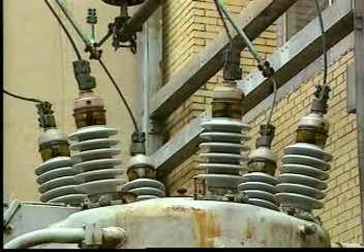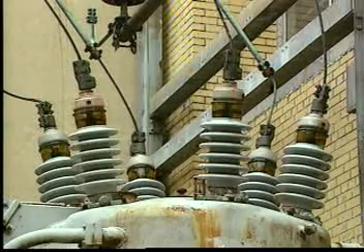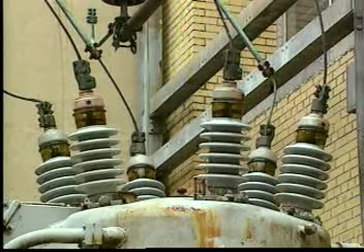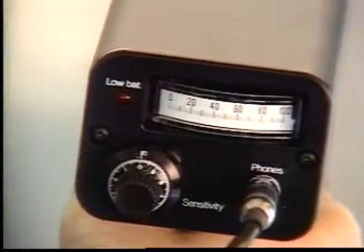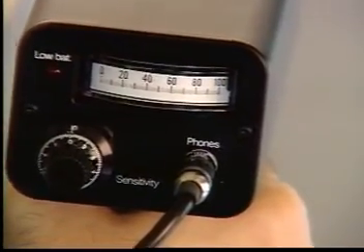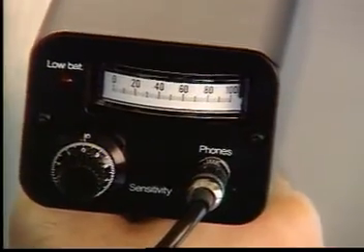Normally, electrical equipment should be silent. If you hear sounds, they may be a constant 60-cycle hum or steady mechanical noises. These will not be confused with the erratic, sizzling sounds of electrical discharge. What you're listening for sounds like a frying egg — uneven and poppy.